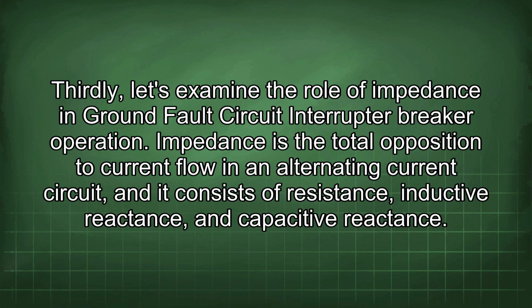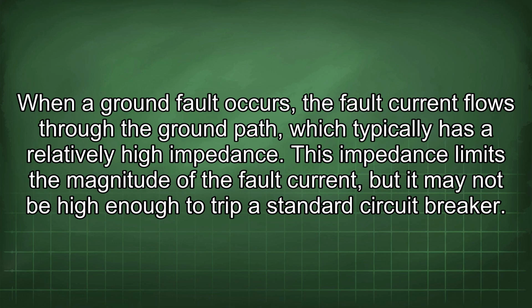Thirdly, let's examine the role of impedance in ground fault circuit interrupter breaker operation. Impedance is the total opposition to current flow in an alternating current circuit, and it consists of resistance, inductive reactance, and capacitive reactance. When a ground fault occurs, the fault current flows through the ground path, which typically has a relatively high impedance. This impedance limits the magnitude of the fault current, but it may not be high enough to trip a standard circuit breaker.